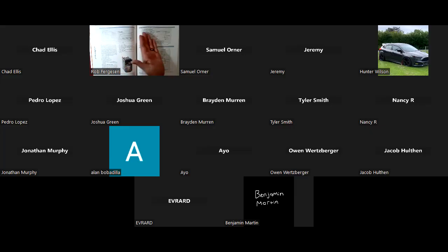And these all come from the faceplate of the motor, so I can set up this stuff and run the VFD for any motor I select. Now, the downside is if you have somebody in there messing around with parameters, they can cause a lot of very expensive damage, right? Whereas in an old school motor starter, it's got the heaters that its designer installed with it, and you can't mess with those heaters very easily unless you physically unscrew them and go find an overcurrent heater. I guess you could do that. But here, anybody with programming access can get in there and mess with parameters.